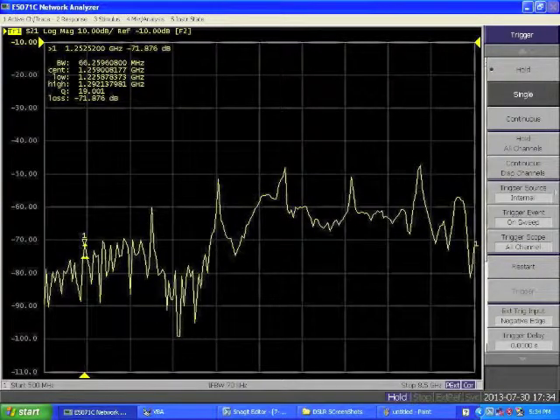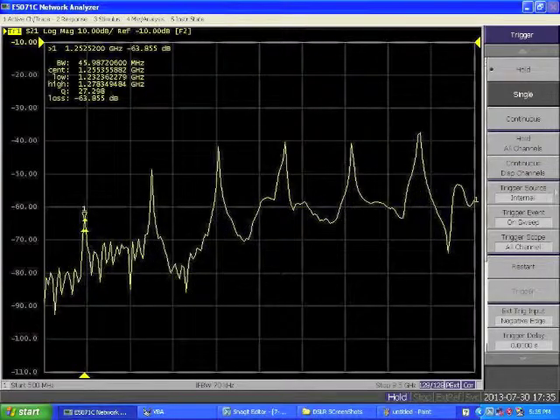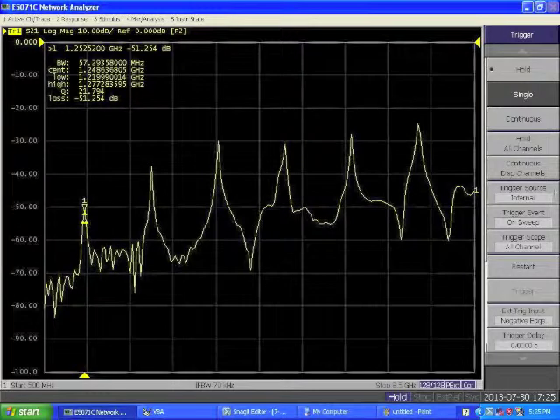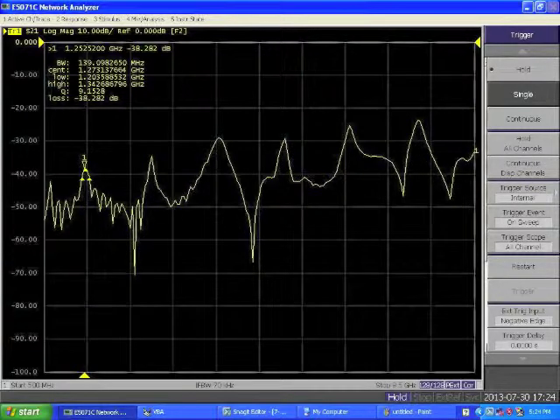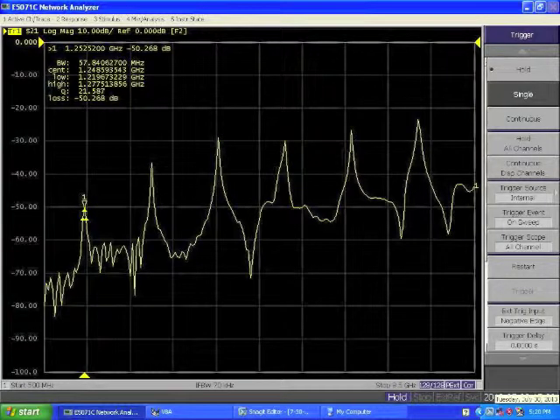As we move the probes closer to the center conductor, we'll start to see the peaks, the resonant modes of the sample start to set in. As we get them closer, the peaks will grow and become prominent, and then we can identify each of those peaks that we need to measure. At some point, however, if we keep adjusting too far, we'll touch the sample and all the peaks will become very broad. That's not a good measurement condition, so we have to back the probe off so it just does not touch, and they'll start looking like this. So there'll be a tiny little gap between the center conductor and the probe tip.